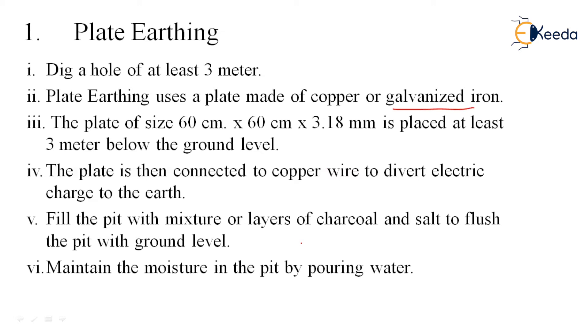First, place the copper plate or galvanized plate at the bottom of the 3-meter deep pit, then connect it with the copper wire. Take out the copper wire up to the earth level. Fill the remaining pit with alternate layers of charcoal and salt up to the level. To maintain moisture in the pit, pour water, because we want minimum resistance to the flow of current. As there is minimum resistance, there will be maximum flow of current — resistance and current flow are inversely proportional.